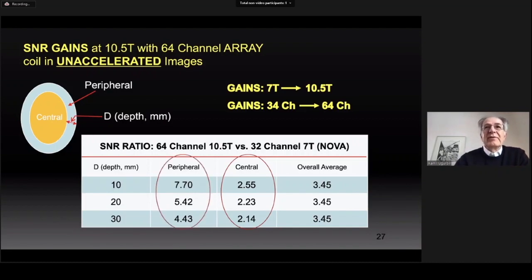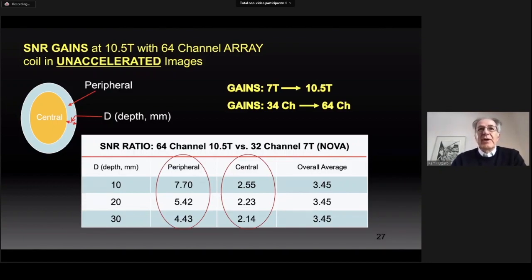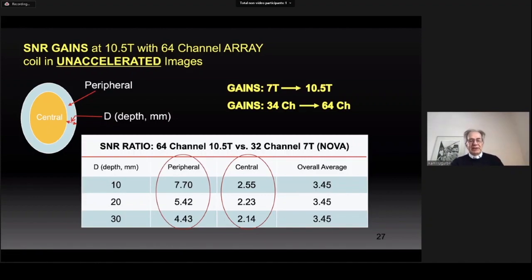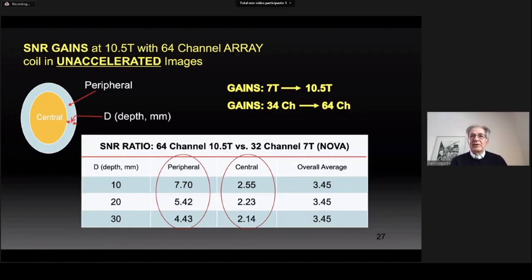In the periphery, however, larger numbers of coils are needed to capture the very high intrinsic SNR, and we have approximately four- to eight-fold increase in SNR relative to 7T, coming from both the increase in magnetic field and the channel count increase. These are fantastic gains that will put us close to achieving not just 0.1 microliter voxel volume but approaching 0.01 microliter voxel volume, albeit only in the cortex.